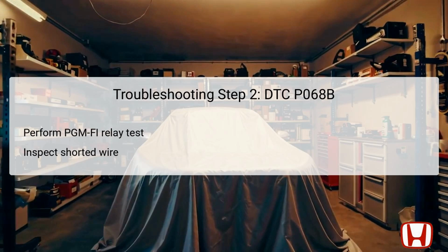Step 2 involves carrying out a test of the PGM-FI main relay 1, as this component is directly tied to the PCM's power supply. Technicians should employ a multimeter to gauge the relay's operational status while observing for any signs of failure. A properly functioning relay will maintain the required voltage levels without significant deviation.